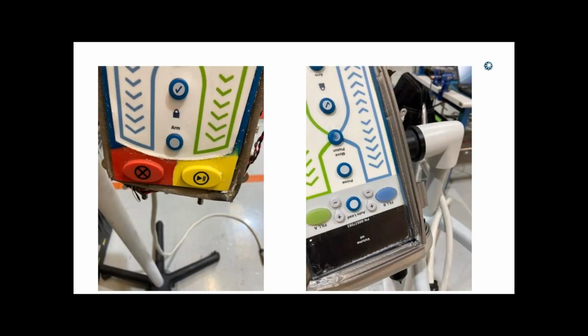That's just on the sealant. That's all contrast. That's on one of those fancy dual overlay gaskets right there. And we actually had them bending down, like I said, hitting the CPU board and giving intermittent 311 errors. That's a real good gasket there, wouldn't you say? Well, lack of maintenance on this guy.